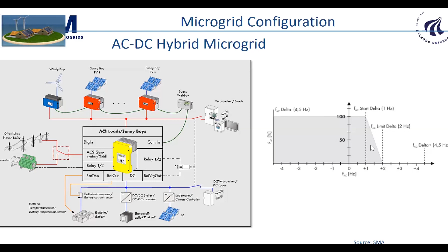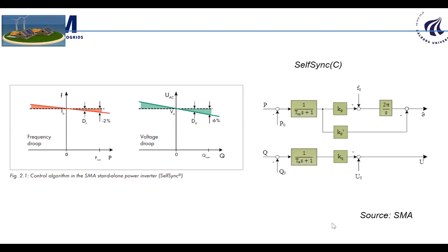What they introduced as something different was a term to directly change the frequency in order to improve the transient response. So we have a frequency-versus-power droop curve, and then they introduced this. Another important thing is that those two filters add additional inertia, something you could assimilate with a synchronous generator, adding the mechanical torque and also the electric excitation. I'll say that was very nicely presented, and it almost becomes a standard.